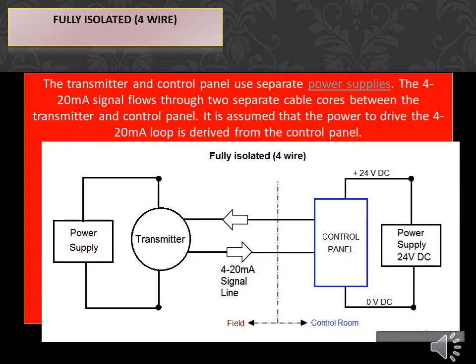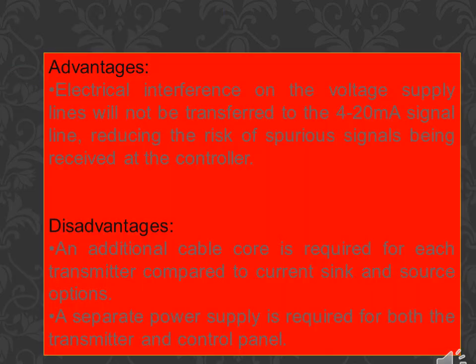Fully isolated, 4-wire. The transmitter and control panel use separate power supplies. The 4-20mA signal flows through two separate cable cores between the transmitter and control panel. It is assumed that the power to drive the 4-20mA loop is derived from the control panel. Advantages: electrical interference on the voltage supply lines will not be transferred to the 4-20mA signal line, reducing the risk of spurious signals being received at the controller. Disadvantages: an additional cable core is required for each transmitter compared to current sink and source options, and a separate power supply is required for both the transmitter and control panel.